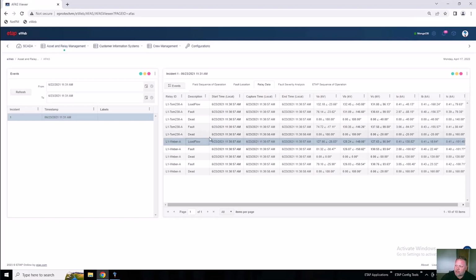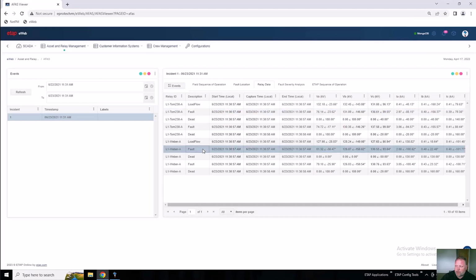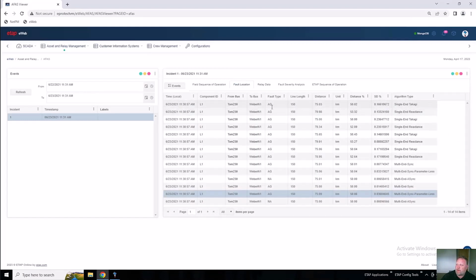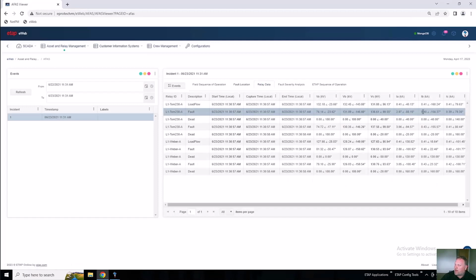What are our normal operating conditions? Then we move on to the fault state. For both of these COMTRADE files, we see the fault state. So when we hit that fault, here you can see my voltage and my current. As I saw earlier in my fault location section, we calculate that it's a fault of A to ground. If I look at my A phase current, it's significantly higher than my B and C phase current. And my voltage is significantly lower than my B and C phase voltage. So that tells me that we have a fault on the A phase, and here's what the characteristics tell me during that state. Also, if you look at L1 Weber A during that fault, you can also see our fault current. So different fault currents are seen on each side.